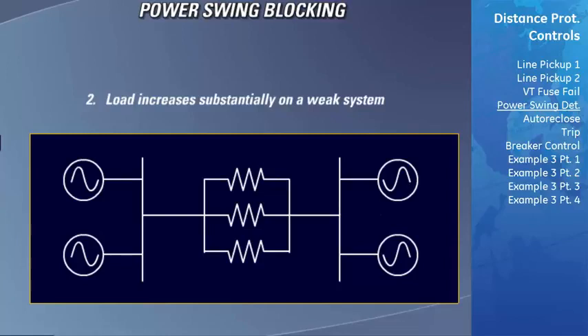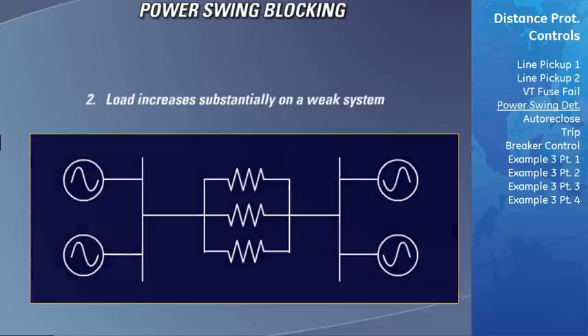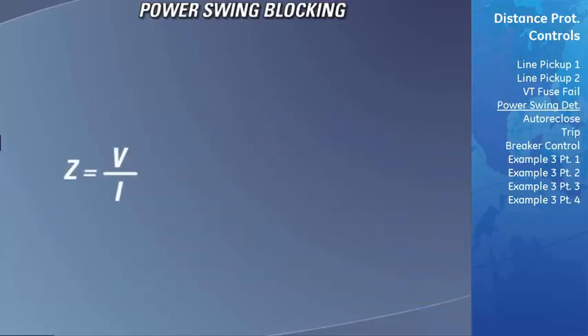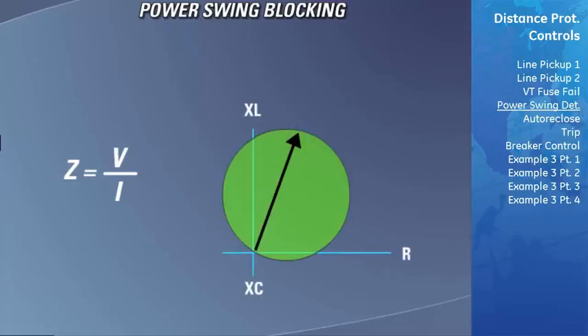During a power swing, the voltages and currents will fluctuate significantly. This fluctuating has a drastic effect on the measured impedance of the line. The plotted impedance as measured by the D60 will slowly swing from our load point into the distance zones of protection, and then back out to a load point if the system regains synchronism.